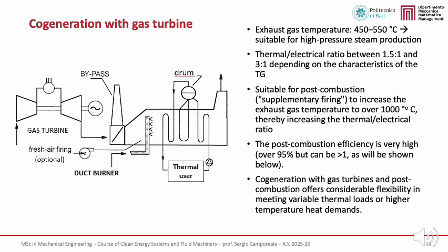An important aspect to note is that the efficiency of post-combustion is very high, often exceeding 95%, and in some definitions, it may even appear greater than 1, because additional useful heat is produced without increasing electrical losses. Overall, gas turbine cogeneration with post-combustion offers remarkable operational flexibility, making it particularly suitable for applications with variable thermal loads or high-temperature heat demand, such as industrial processes and steam distribution networks.